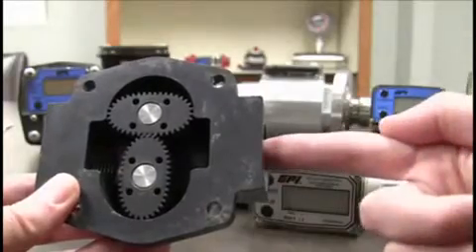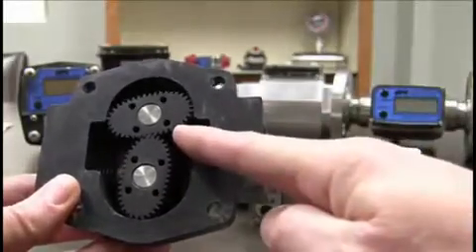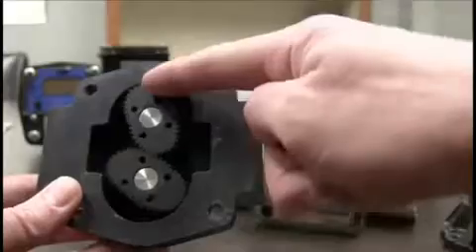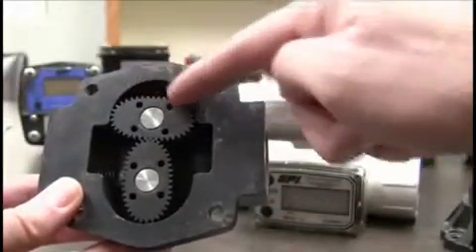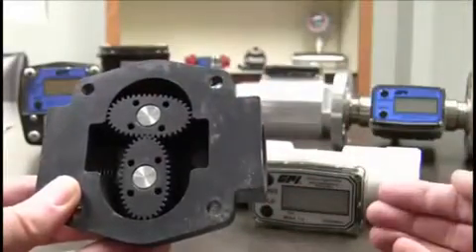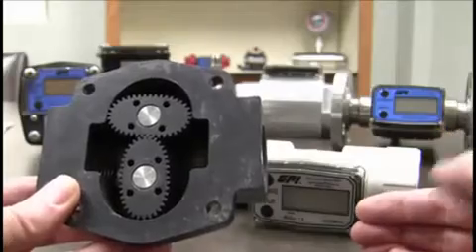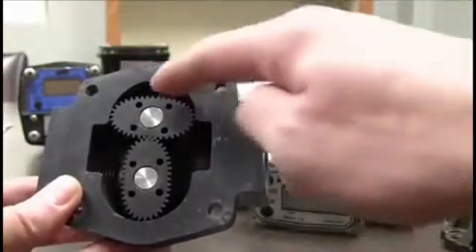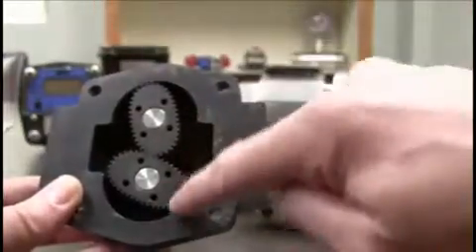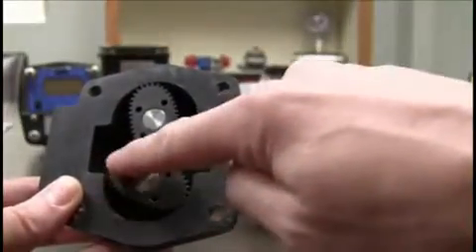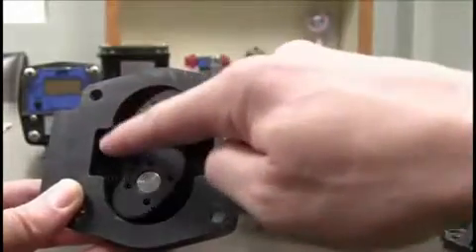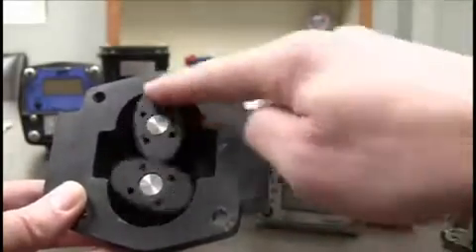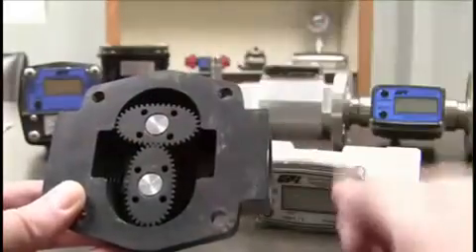So if you have your fluid coming in this way, it's going to come in through here. And you get a little chamber of the fluid right there. And that chamber never changes size. So it doesn't matter if it's thick like oil or thin like water. That chamber always holds the exact same amount of fluid. So it goes through and pushes on out. Same time, this side, another one's going. So it just keeps going. And so really the fluid's going this way. It looks like the rotors are spinning backwards. But it pushes the fluid right on through and counts it.